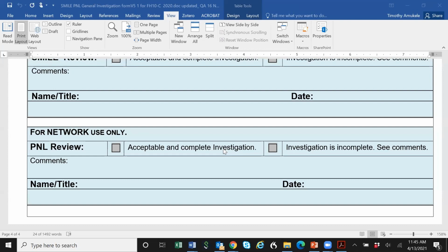Or something we've done, but we don't do it often. The lab where I am now, I left Johns Hopkins to run the laboratory portfolio for a company called Icon. And one thing we've done is, for analytes that are hard to get, we try to create a large batch control and save it as aliquots in the freezer ourselves. Something like that can help, but likely mostly just comparison with other labs if you don't have the original EQA material.